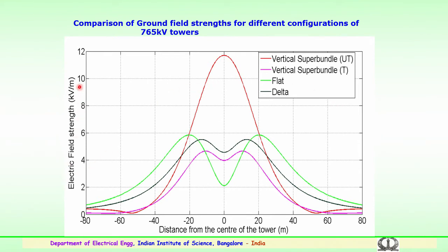Here you can see the electric field in kV per meter versus the distance from the center of the tower. Very clearly you can see when the conductors are transposed, the levels of electric field stress reduce. This is again in case of delta, the pink color shows the vertical super bundle, whereas for untransposed the electric field strength is very high, near 11 or 12 kV per meter. For the same tower with the transposition, it comes down to 4, so it reduces by one third. So the very clear conclusion is that going in for transposition will be the better option for reducing the electric fields.